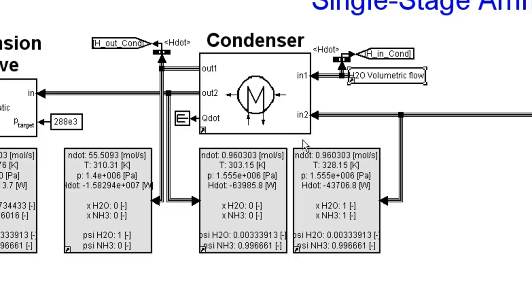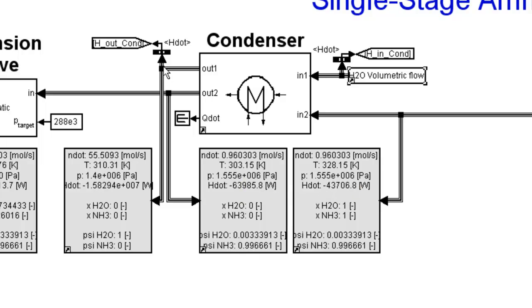As it exits the condenser, this is the second display over here, we can see that it cooled down by 25 degrees Kelvin. Now it's all liquid. The concentration is, of course, still the same. The output water heated to 310 degrees Kelvin. That's like 7 degrees higher than the 303 degrees we input there. And the water is all liquid.